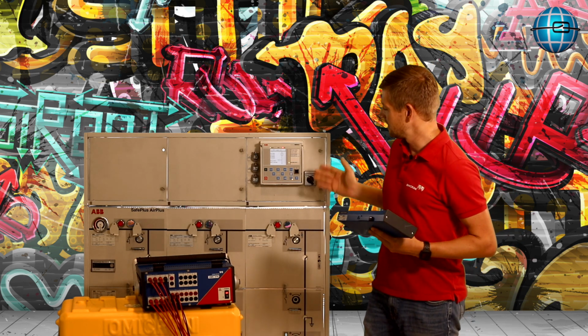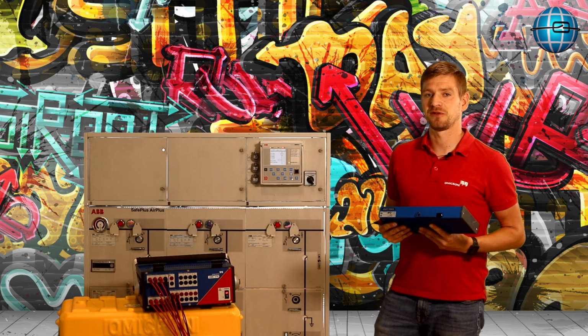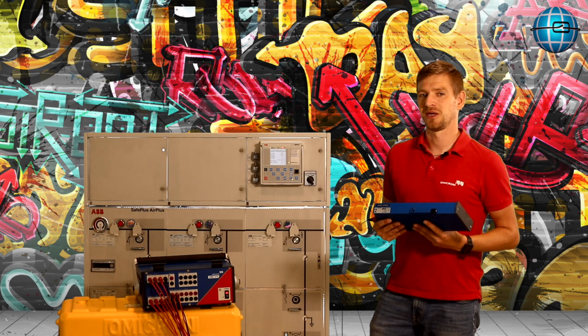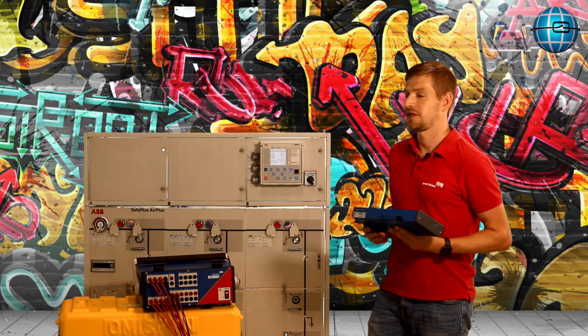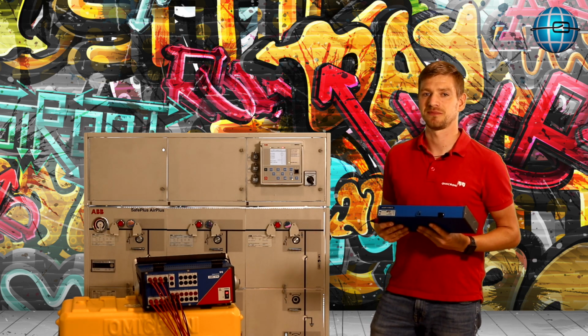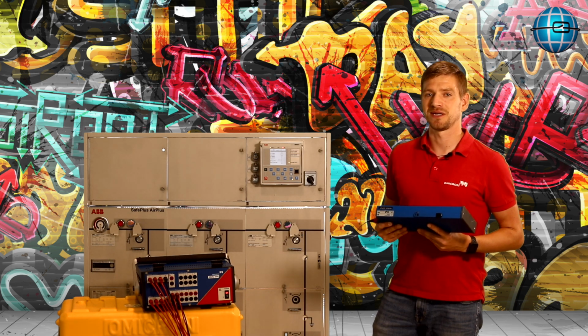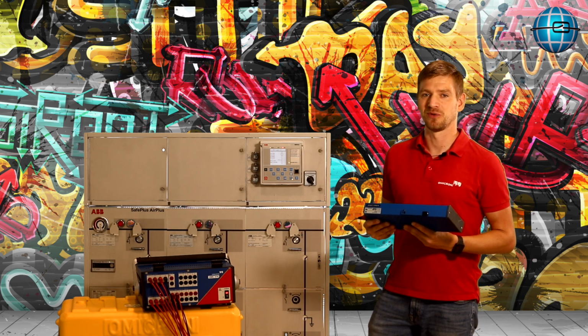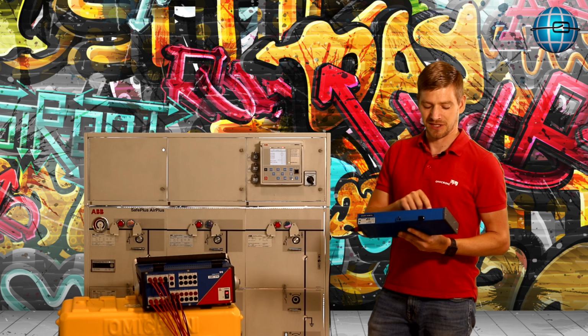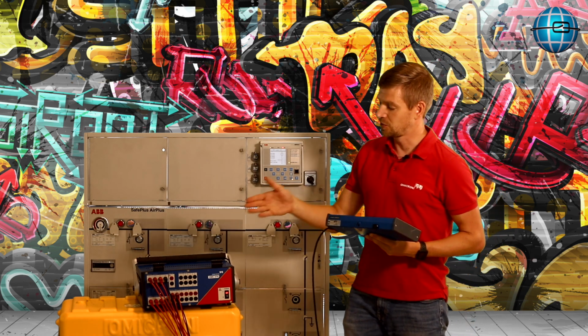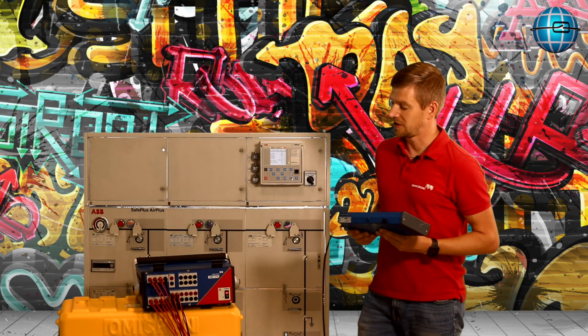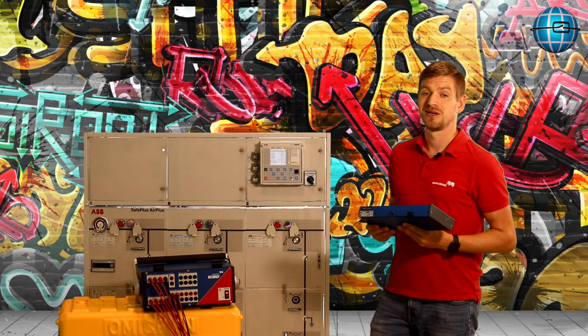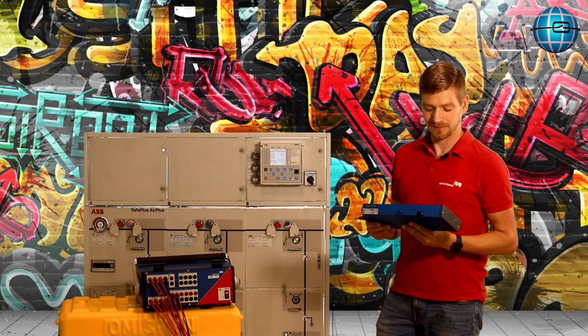So I've connected here a protection relay where I have configured a two-stage overcurrent protection and an overvoltage protection. And I will test both of them by secondary injection with my CMC 310. Therefore, I start with CM control with the hardware configuration to configure everything I have wired up here. So 3-phase current and 3-phase voltages, and in addition a trip and a start signal.